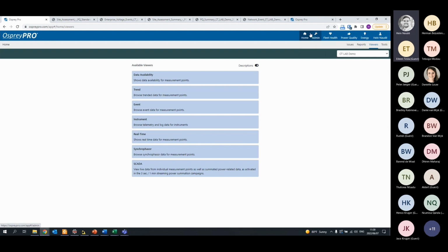If I do an event analysis, it's difficult to show you now because I'd need to search for an example. But what I look at firstly, if you have multiple measurement points on the network, is whether you see fault current anywhere in the network. If you obviously see a fault current in your network, then you know there is normally a fault within your network. You can also look at what your voltage dips do.